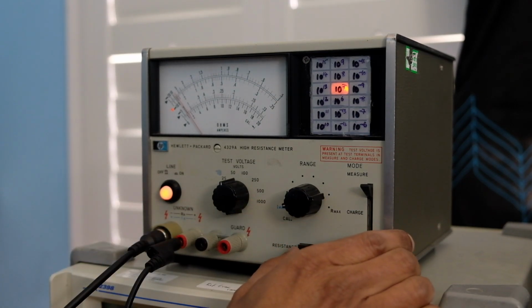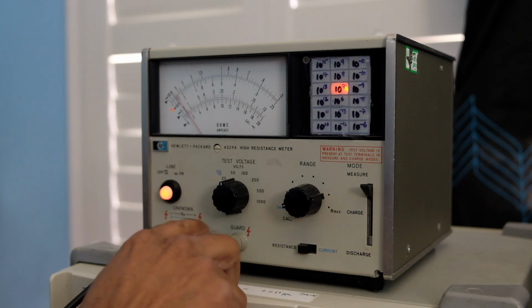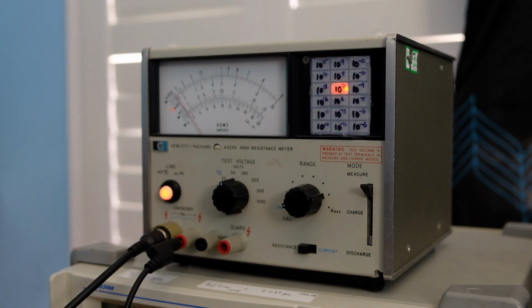Besides that, there's a current setting, as I mentioned. There's a guard, of course, if you want to apply a guard to the cable measurement, and if you're really measuring teraohms and gigaohms, you would probably have to try using that guard to make sure you don't pick up unnecessary leakage. So this basically concludes the demo and brief description of the instrument.